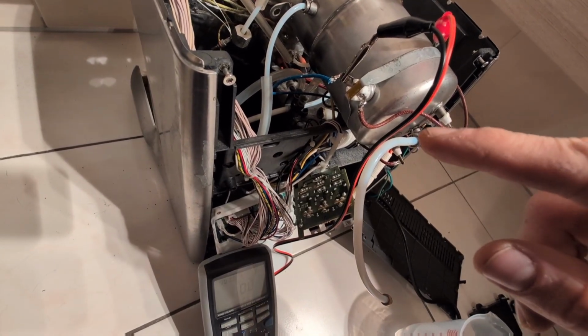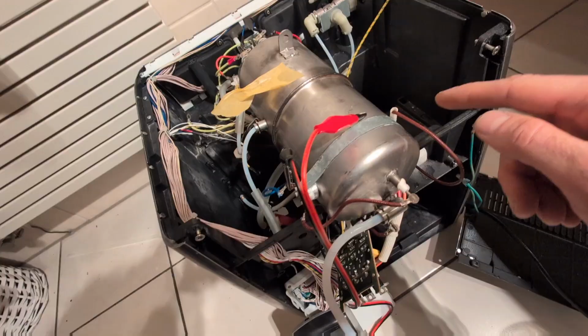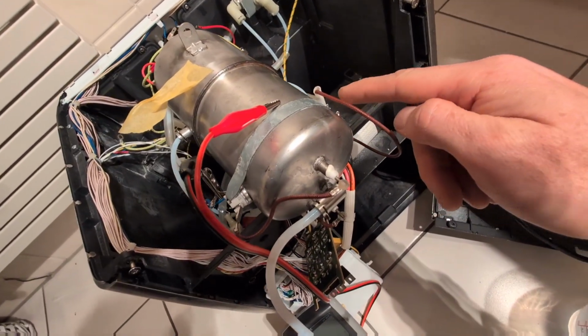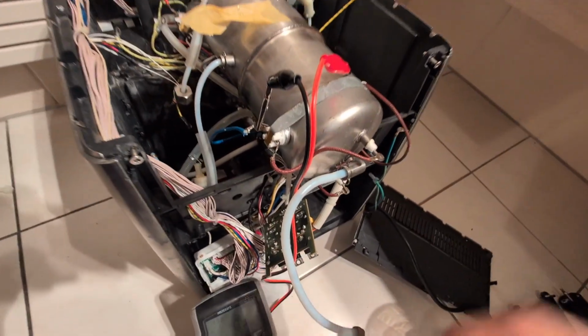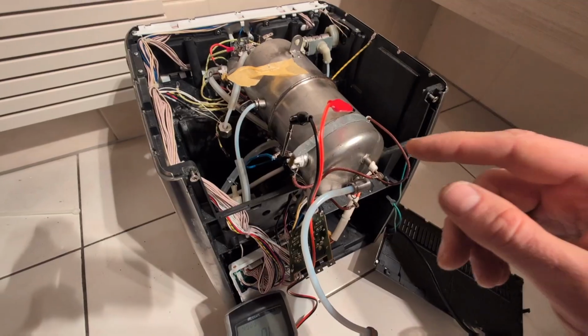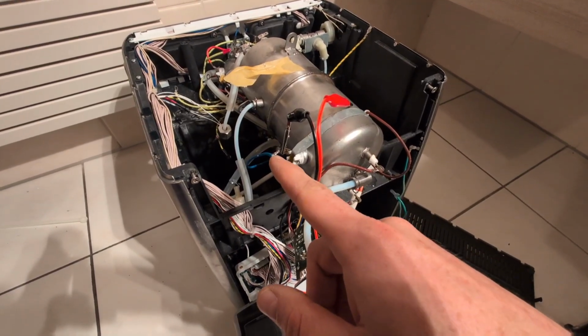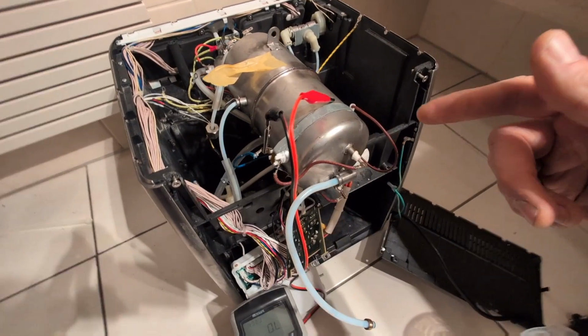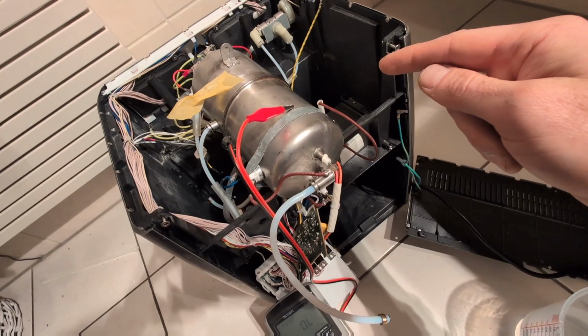So if the boiler gets warmer, the thermostat cuts the circuit. But if it's not working properly, the current goes through and reaches this thermal fuse, rated to 155 degrees Celsius. If the thermostat isn't working properly and the boiler overheats, the fuse gets blown.